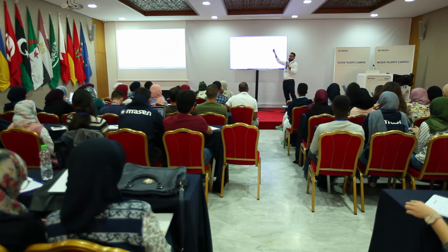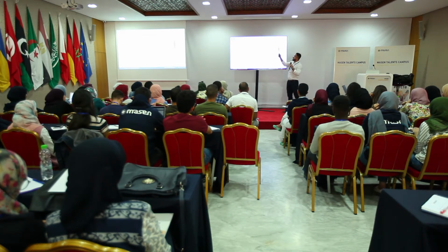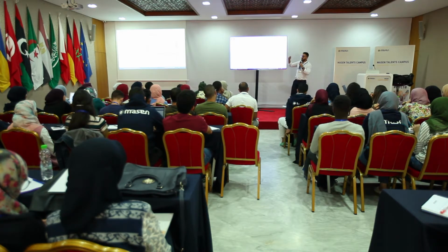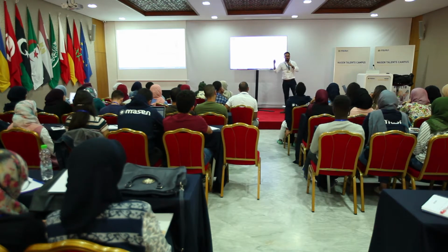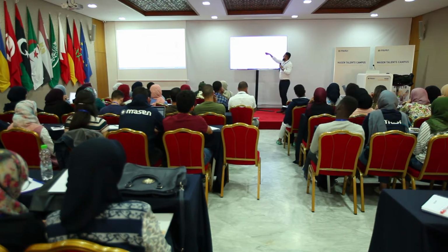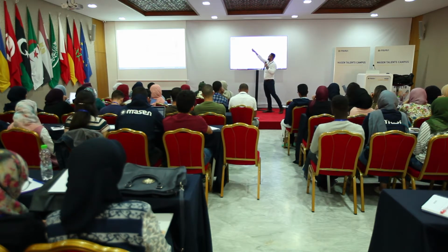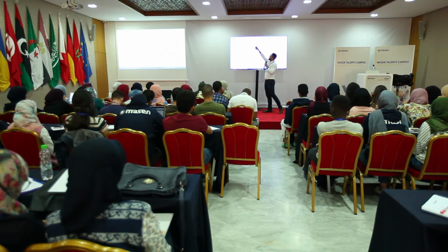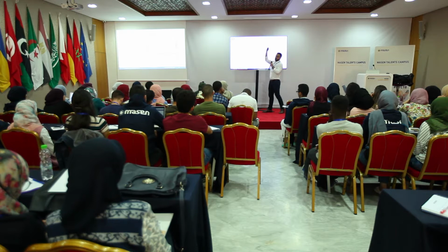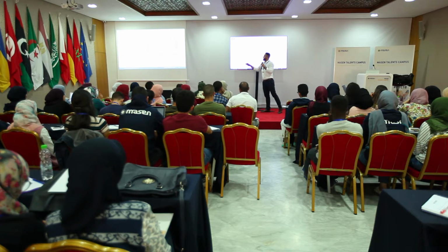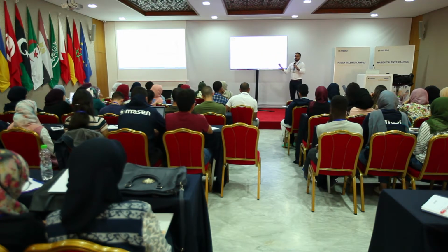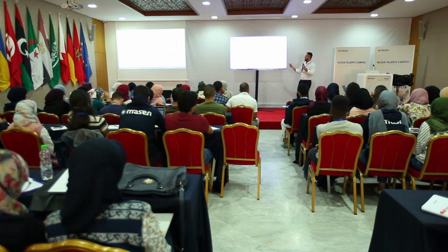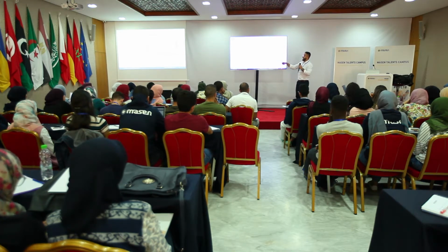So is it clear? You see, this is the flexibility of a CSP plant. And you see how it's actually challenging to design, because if you design for a summer day, this is your design condition, a lot of solar energy, this is what will happen. If you design for a winter day, this is your design condition. You have less energy, and then you need to see how you operate it. Of course, anything in between will happen in the equinoxes. But the CSP plant gives you the flexibility to do that. And you see that even in winter, we could guarantee for most of the high demand hours all the nominal capacity. We just lower it during the midnight so that we could never shut it down. That's the only reason why we did it.